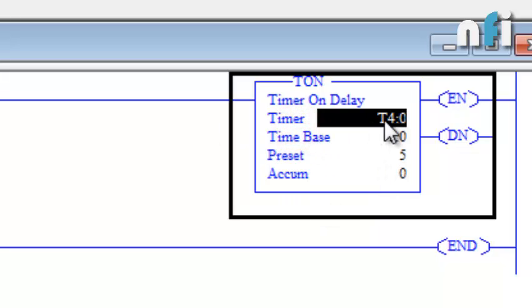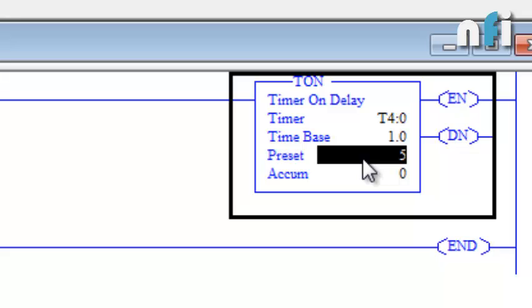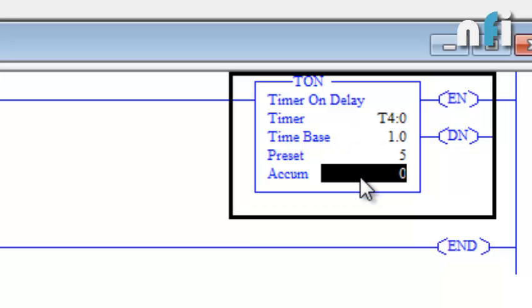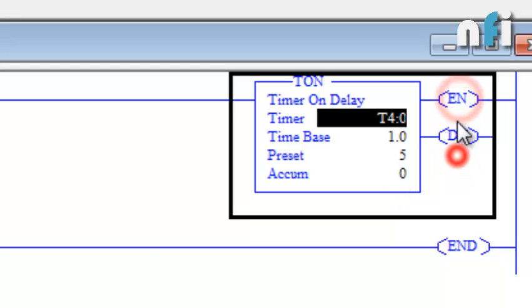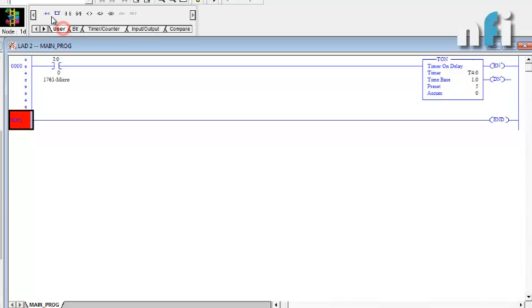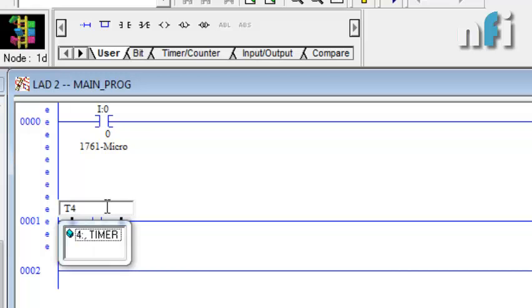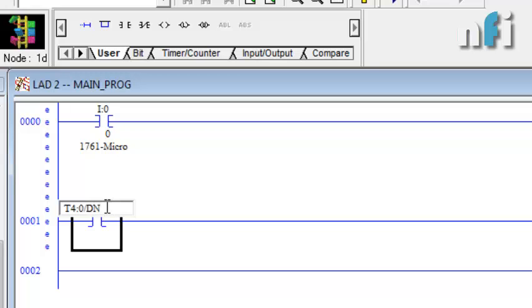The timer address is T4:0, the time base is the unit of the timer, the preset is the delay we want, and the accumulator is the real time the timer counts when it turns on. There are two bits: EN (Enable) and DN (Done). Enable means when the timer is on by pressing I0, the enable bit will be on. The done bit will be on when the timer completes its time, or when accumulator equals preset. To use the done bit, we write the address T4:0/DN in a NO contact.